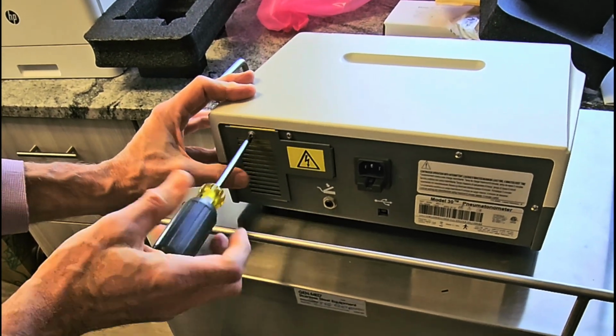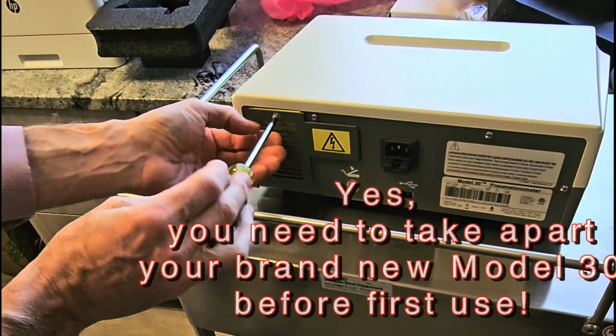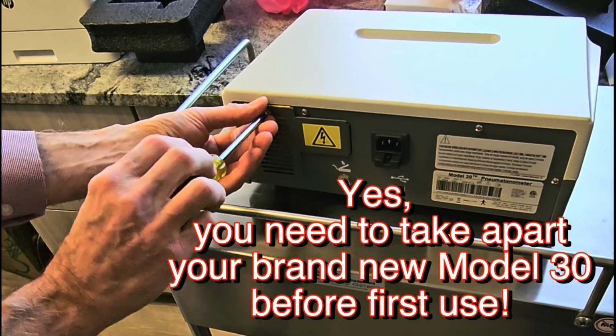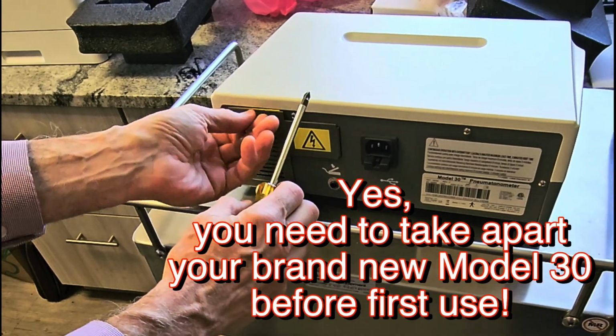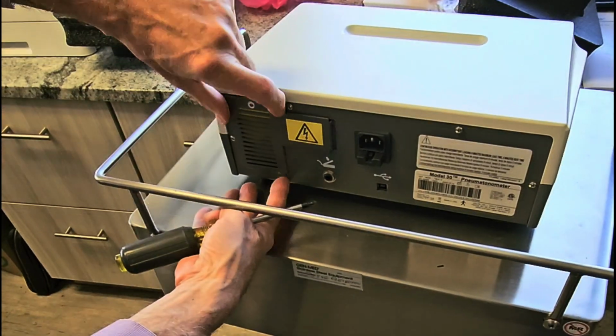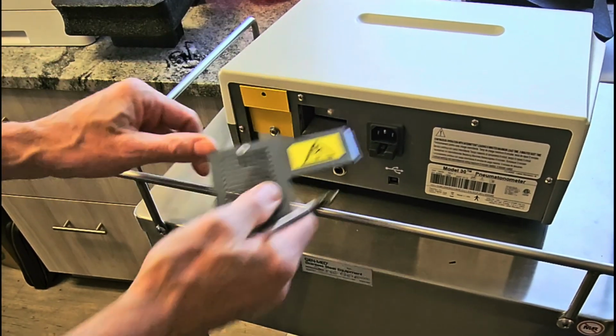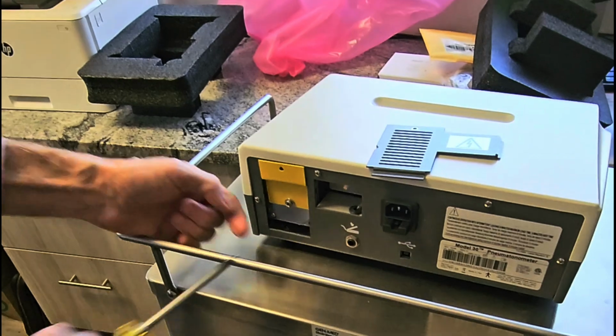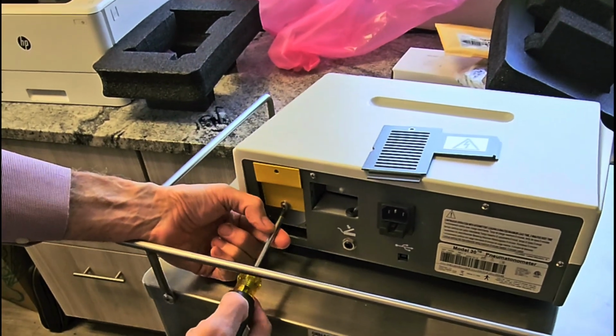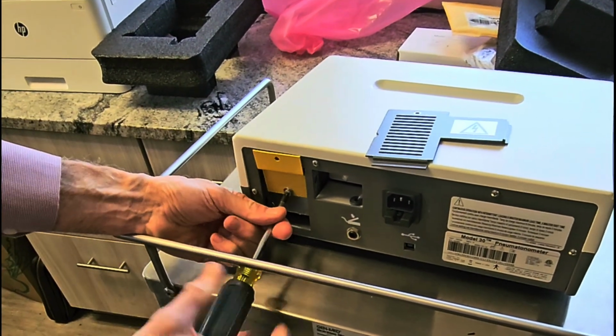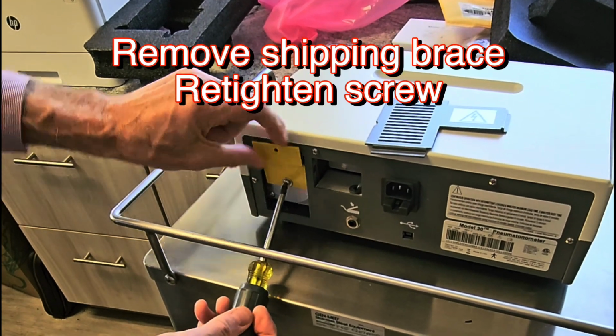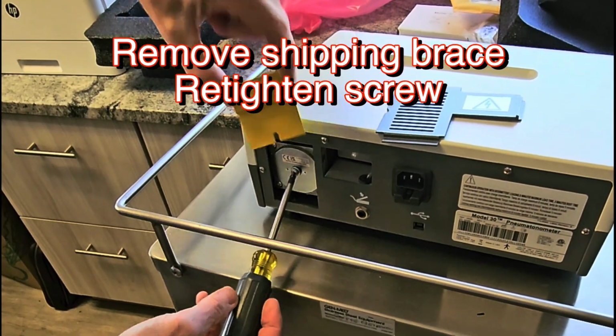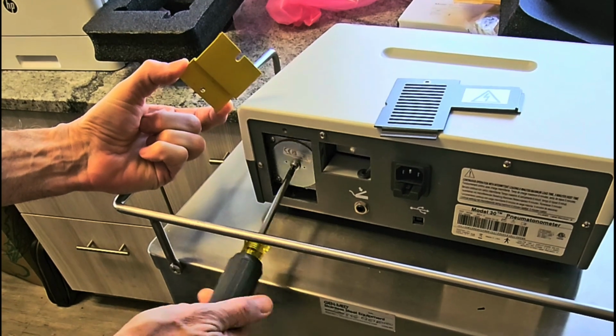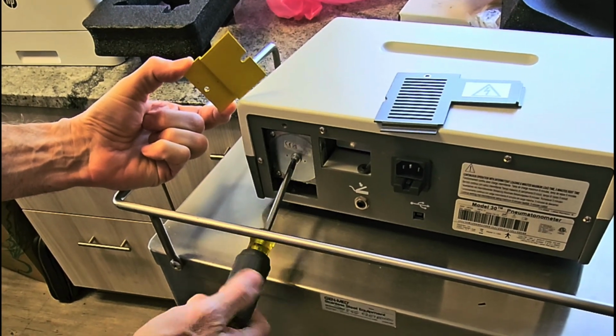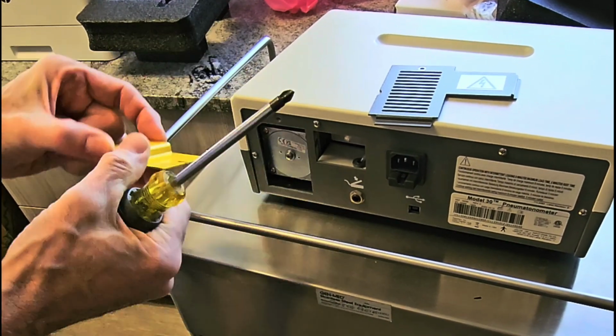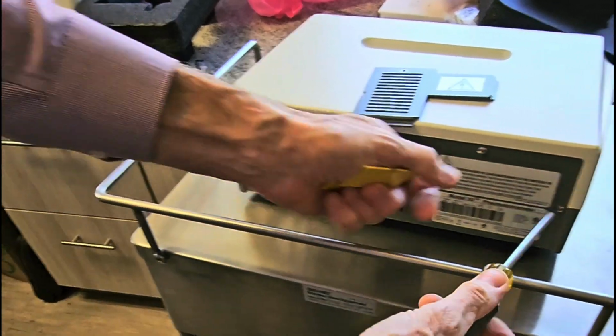So start by taking out a Phillips screwdriver and unscrewing the back. Yes, you need to take apart your brand new Model 30 before you use it. And here's why. So behind there is a shipping bracket, and what that does is it locks the motor in place so that it doesn't get damaged as the thing is shipped around. There's a suspension system on the motor to decrease vibration. You can now see it all free and moving, and that has to be locked in anytime the unit's shipped.